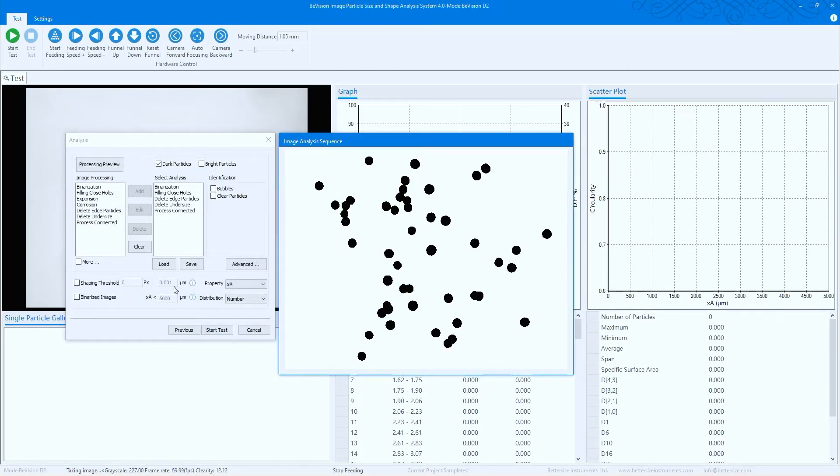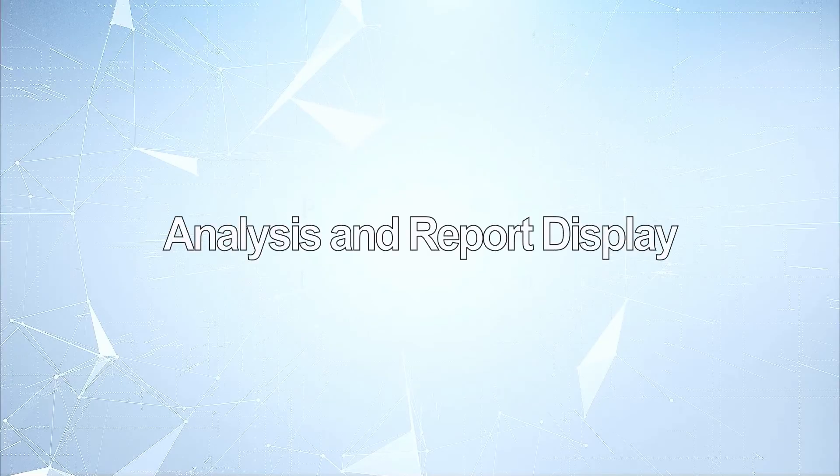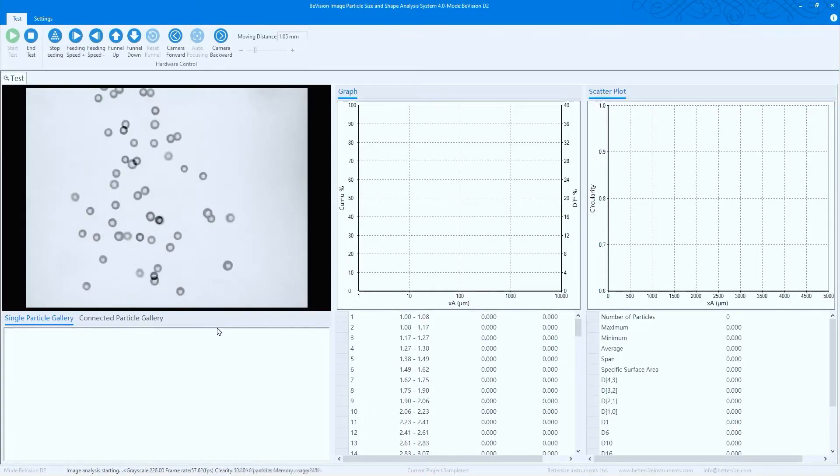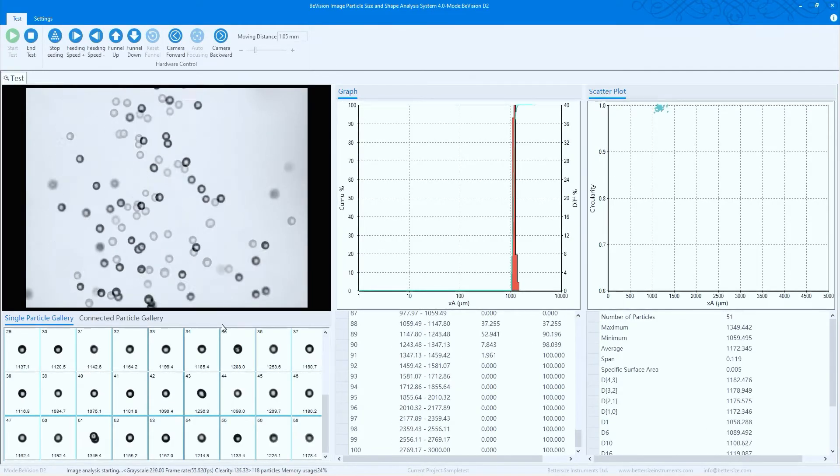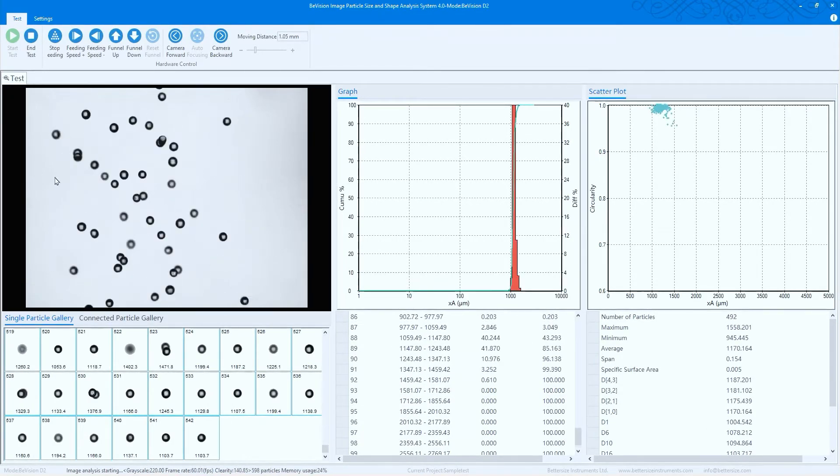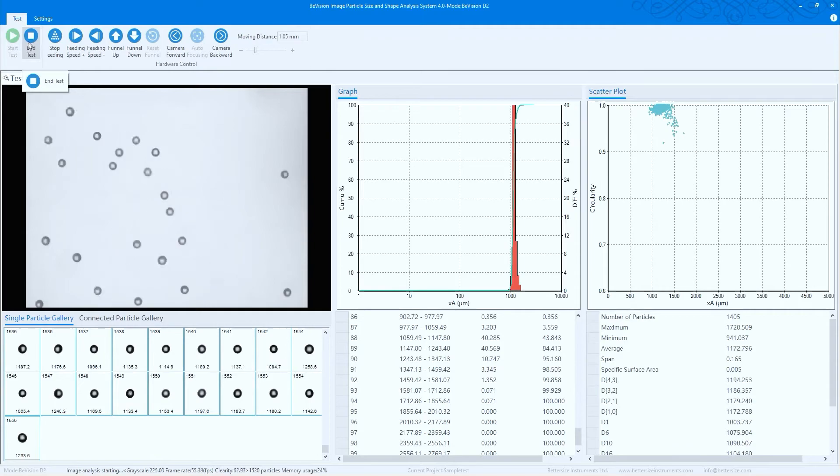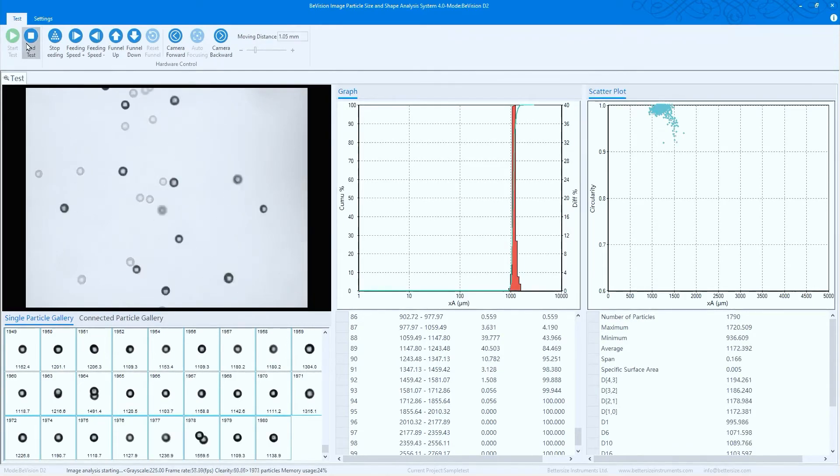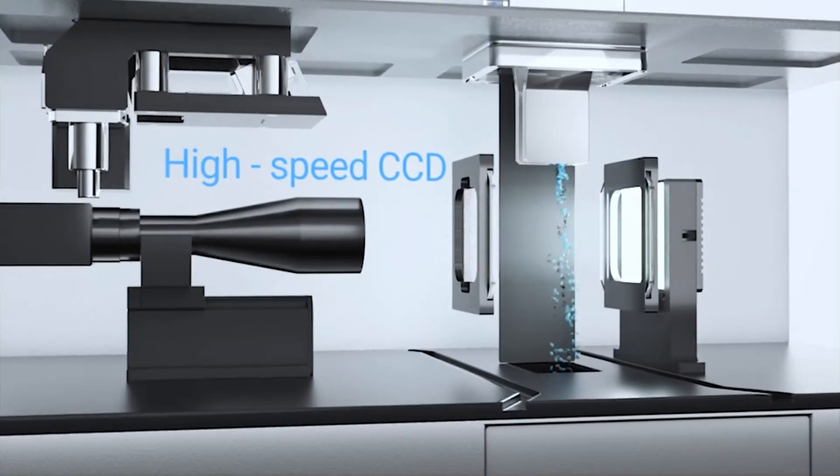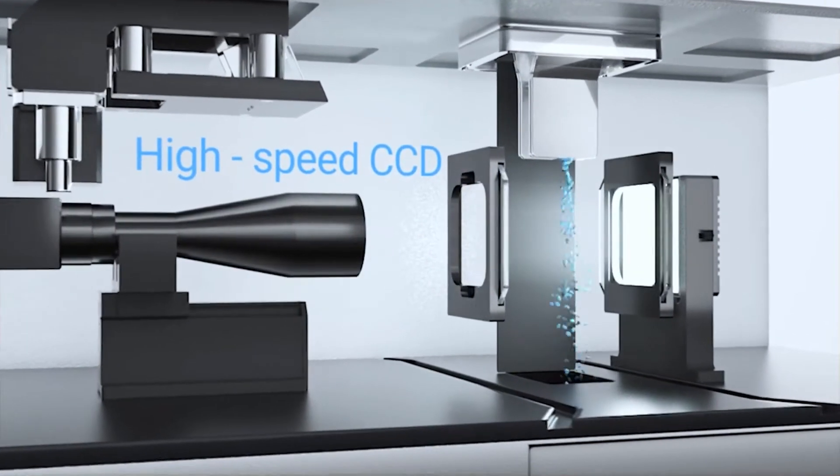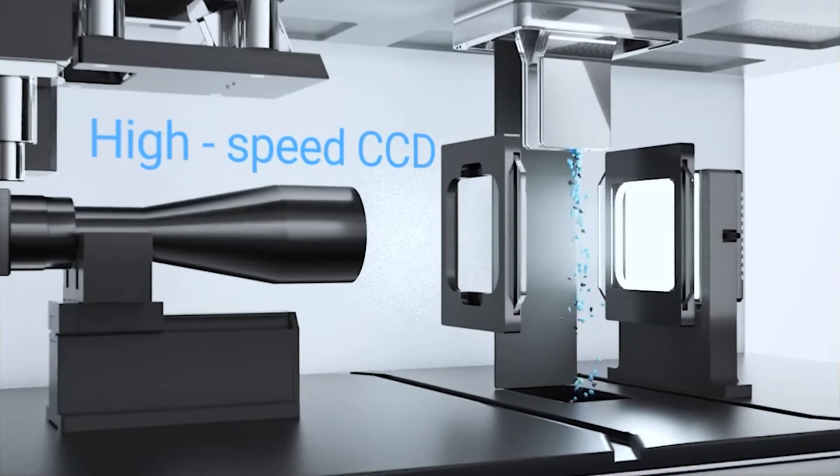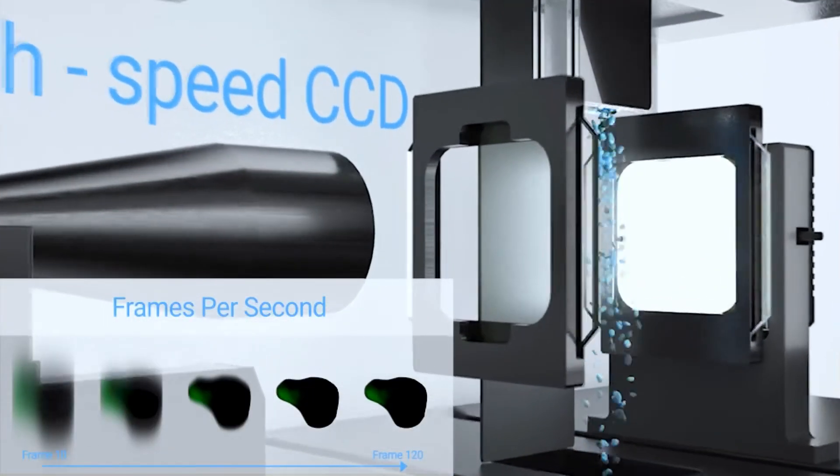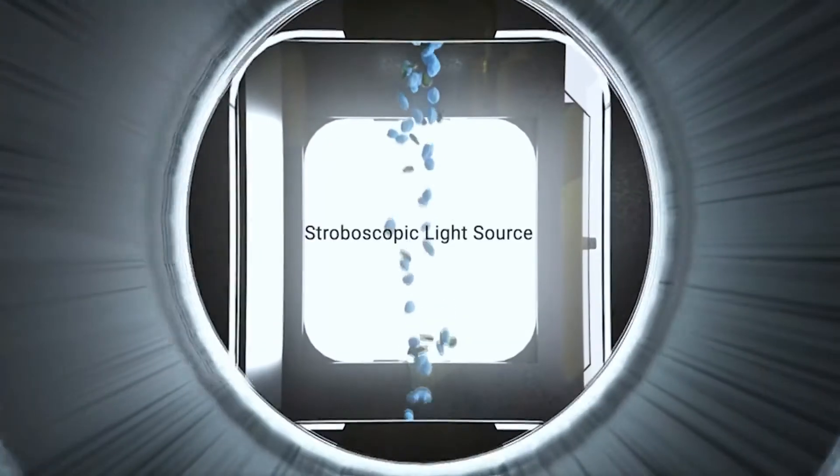Start the test now. You can see that the particles are moving into the BeVision D2. Once the particles flow through the sample cell, the integrated high-speed CCD digital camera will start taking images of each particle at a rate of 120 frames per second.